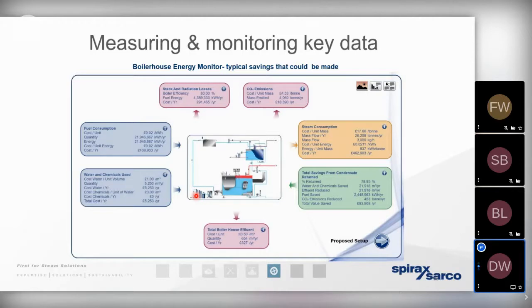For example, moving away from manual blowdown controls to install automatic timed blowdown controls. Will there be a benefit to fitting an economizer on the flue? How much condensate is being returned? How much flash steam is being vented away? Is there an opportunity for heat recovery from the TDS blowdown and so forth? It means that we can really start to get an understanding of the projects that will allow an enhanced operation, a reduced cost of fuel, and a reduction in carbon emissions within the boiler house.